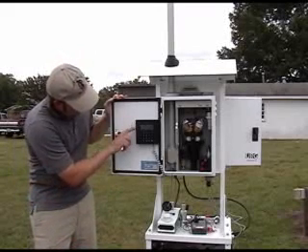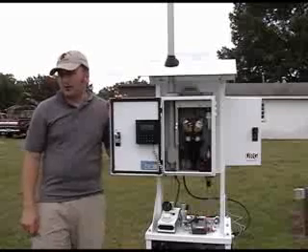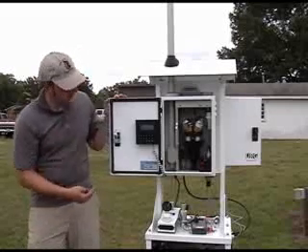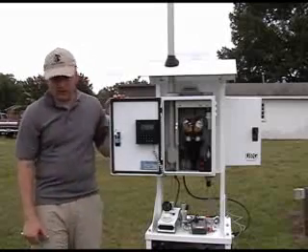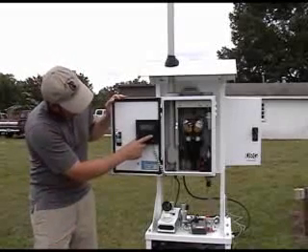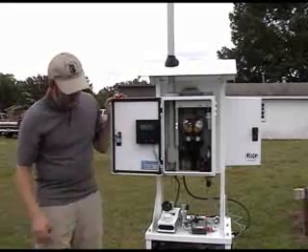The next one down, F2, is view gain offset. Those are our flow calibration parameters. Those aren't set yet because we're doing the calibration. And F3 is the temperature and barometric pressure calibration parameters. And lastly, one more F4 down is our site configuration.